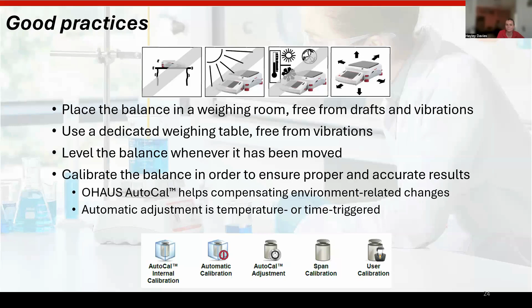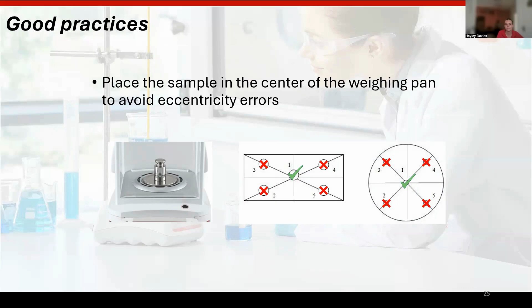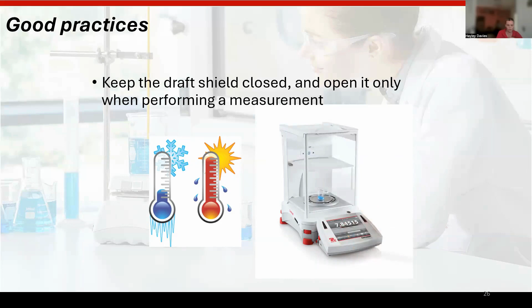Always when you are weighing, make sure you place the sample in the center of the weighing pan to avoid any eccentricity errors. So don't pop it on the edge. Make sure it's as much in the center as you can. If you've got a balance with a draft shield, keep that closed at all times unless you are performing a measurement. All of the Ohaus balances, anything 1 milligram or 3 decimal place and above, will be supplied with a draft shield. So keep that closed, and only open it when you are doing the measurements.